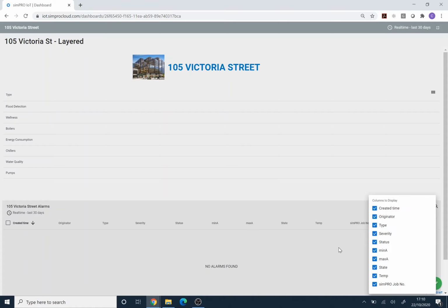Each alarm shows details on the equipment at fault, sensor thresholds and the measurement that has triggered the alert, and you can choose to show as little or as much of this information as you wish by checking the relevant boxes here. If using a compatible job management system such as Simpro, work orders can automatically be generated against an alert. That job can then be directly accessed from the alert entry. Now let's take a quick look at the areas of the building now being monitored, starting with flood detection.